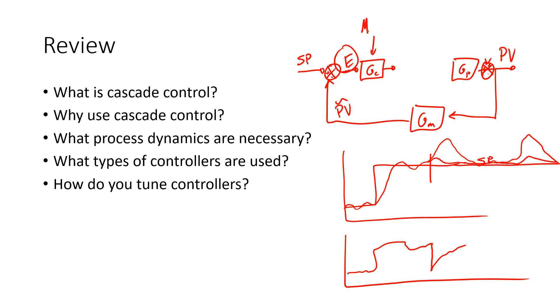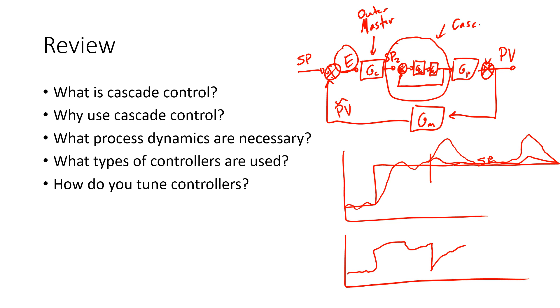We have this controller — we'll call this the master or the outer loop controller. That's going to provide a set point to the inner loop. Then I'm going to have another summing junction, and then a second controller. That's going to change the valve, and then I'm going to have something like a flow with a feedback there. So this is an inner loop right here, and that's when we have a cascade. We call it a cascade because the outer is giving a set point to the inner — we're cascading these set points down.